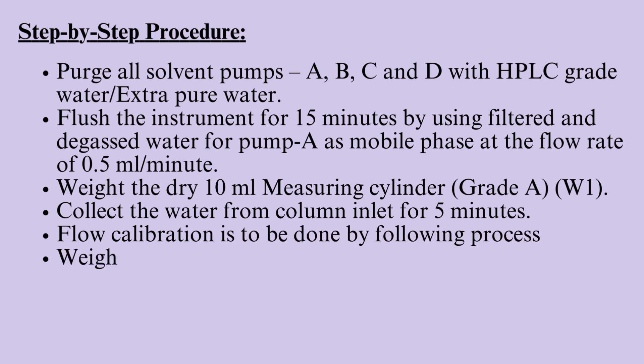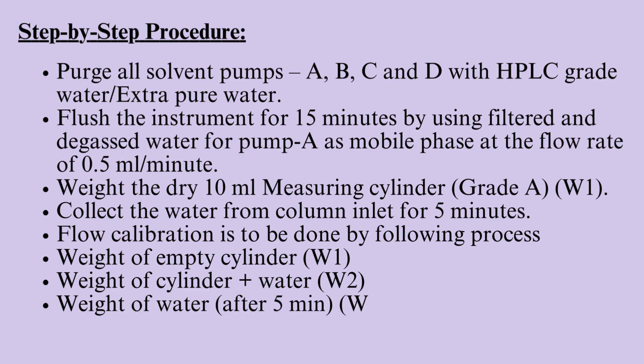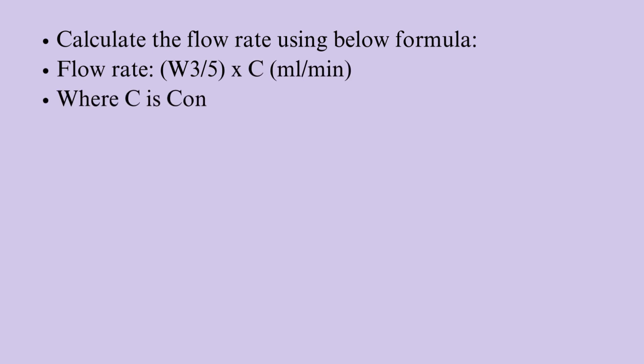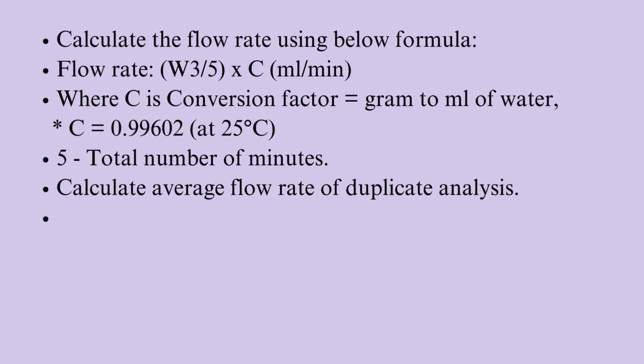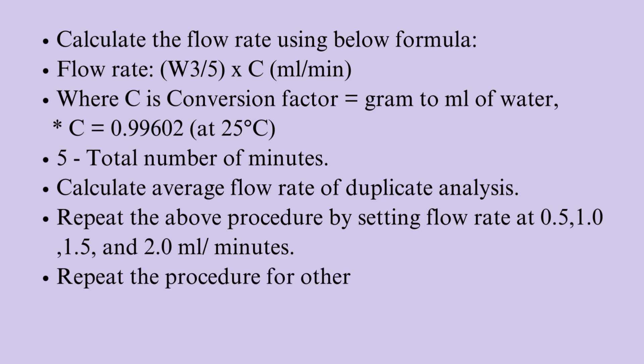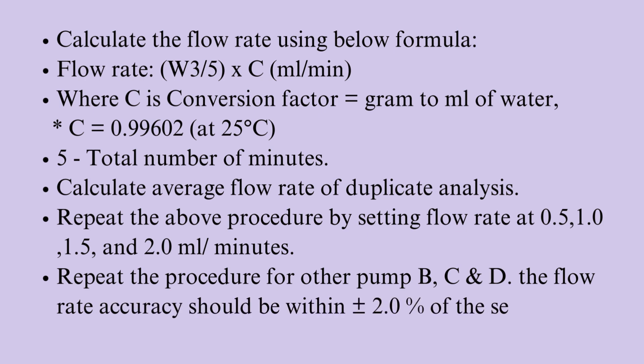Flow calibration process: weight of empty cylinder W1, weight of cylinder with water W2, weight of water after 5 minutes W3 equals W2 minus W1. Calculate the flow rate using the formula: flow rate = W3 / 5 × C ml/min, where C is the conversion factor (grams to ml of water), C = 0.99602 at 25°C, and 5 is the total number of minutes. Calculate the average flow rate of duplicate analysis. Repeat the procedure at flow rates of 0.5, 1.0, 1.5, and 2.0 ml/min. Repeat for pumps B, C, and D. The flow rate accuracy should be within ±2% of the set flow rate.